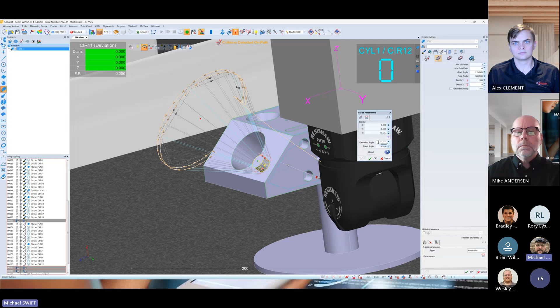And one thing I would like to adjust is that I see that I have a lot of frame motion, and that's indicated by the peach lines here. In this scenario with this feature, the frame has to move around in addition to the AB for accessibility, so I don't shank out, so I don't crash. Though 30 degrees, which we see in this parameter here, is fine, I can actually change it to 40 degrees if I wanted. We allow you to do that, but we can also see a different indication of the colors saying you're approaching the unsafe zone, or the area where you may not be collecting the best possible data within the manufacturer's stated requirements. So we're going to show you that graphically.